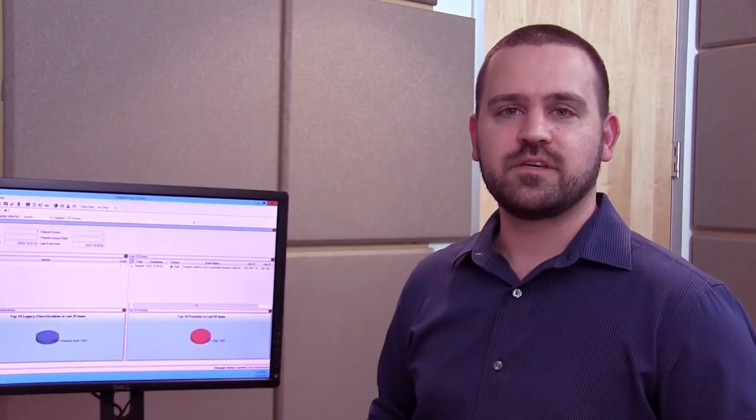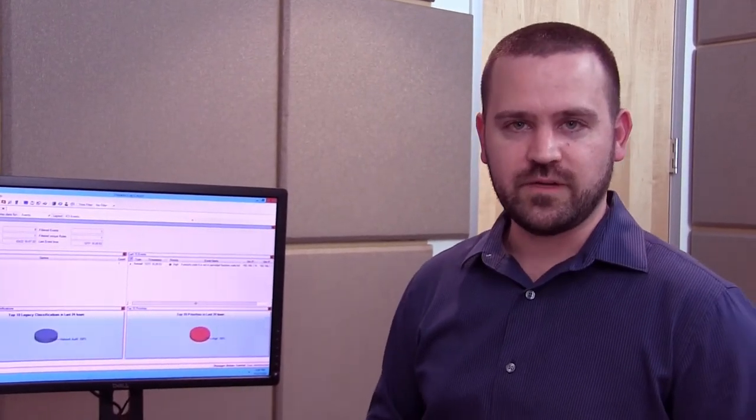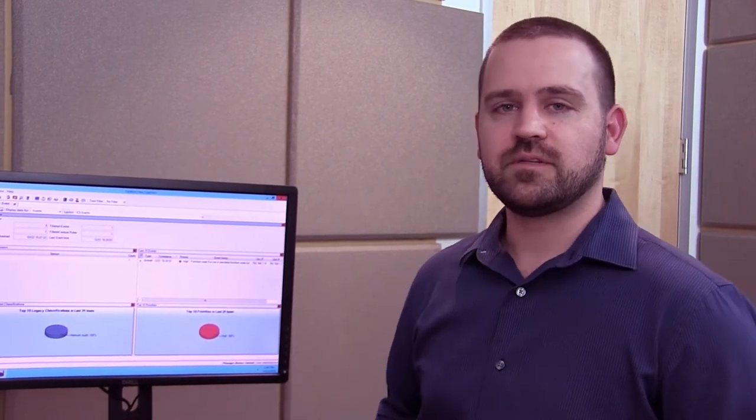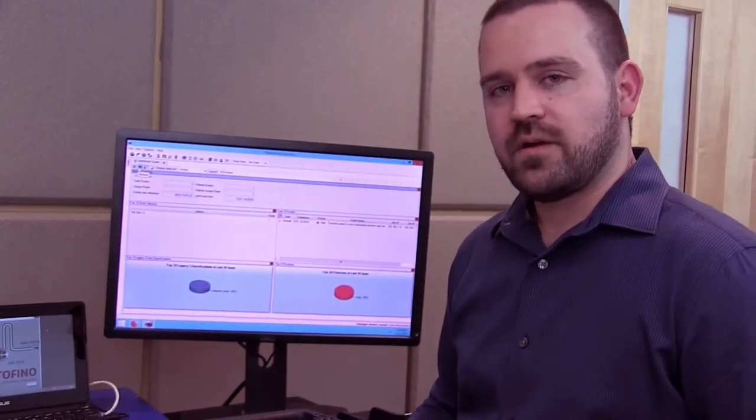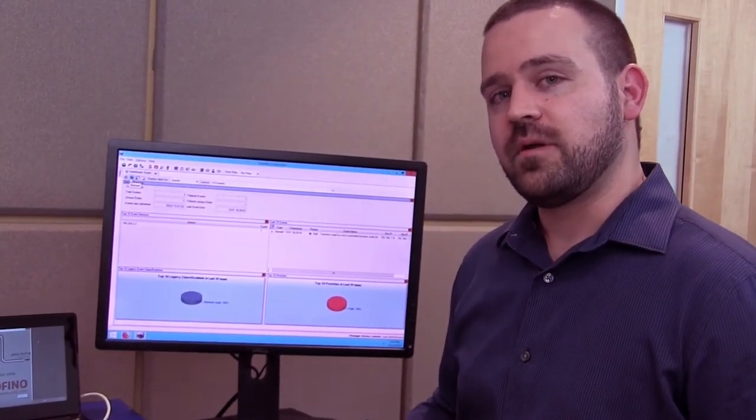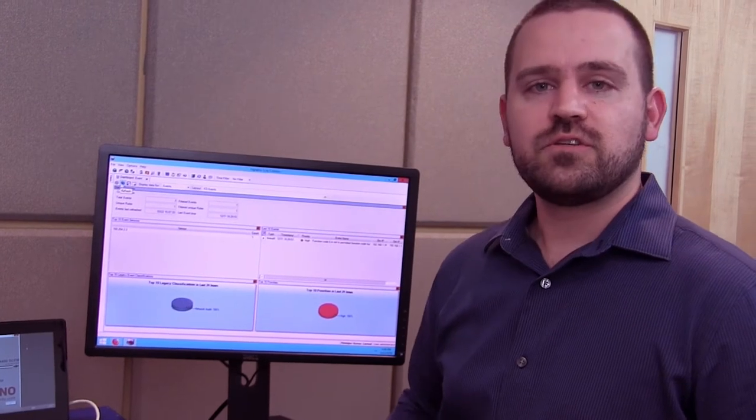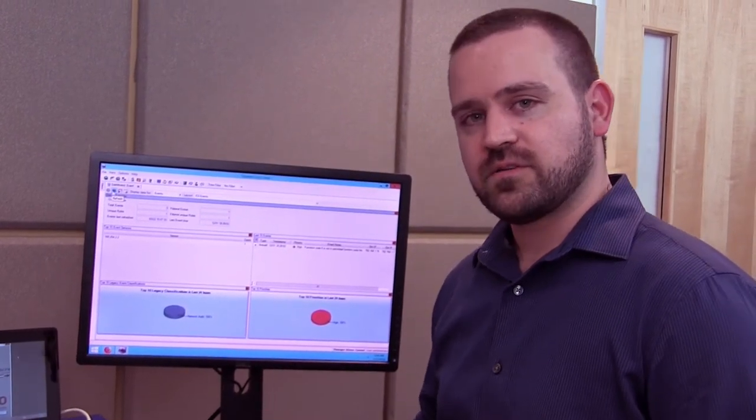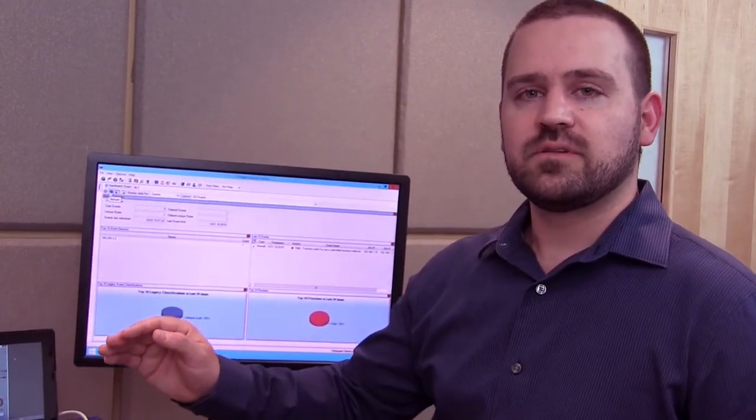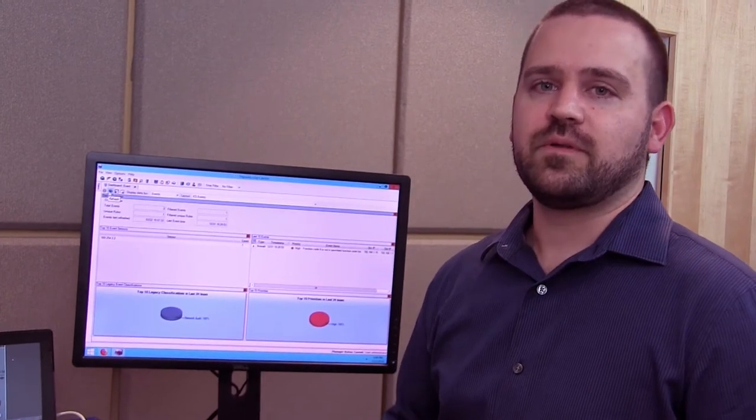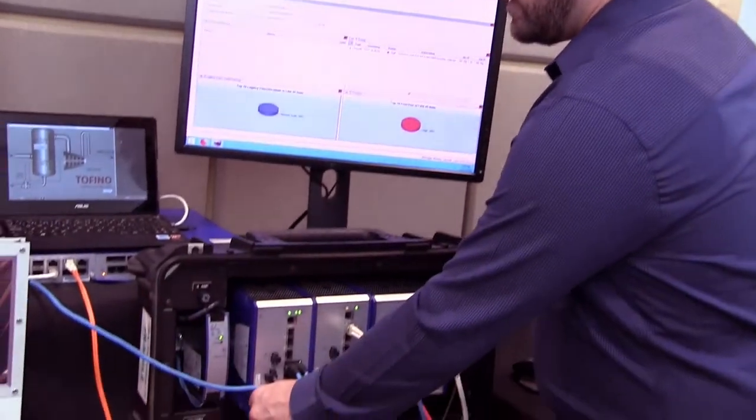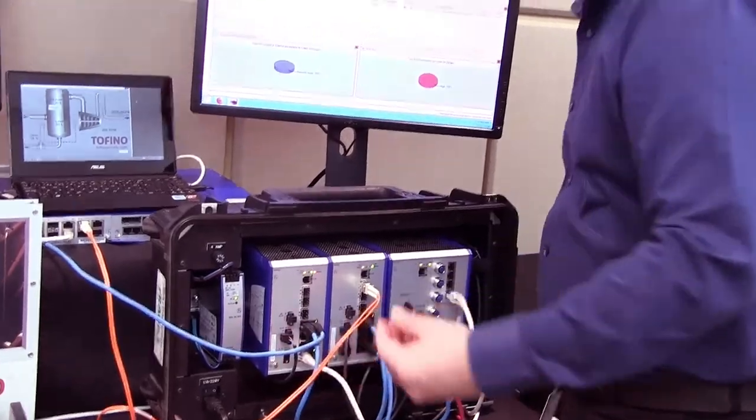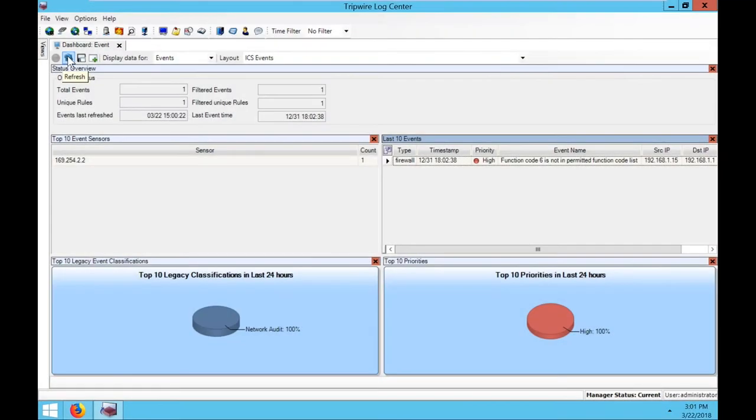It's important to note the security can also be very operational in nature. For example, in most industrial networks, we have redundancy built in everywhere, but one of the complaints I often get is if a redundant power supply goes down or if a primary power supply goes down, you actually don't know until two years later when the redundant power supply goes offline also. For example, if we pull this power supply to simulate an outage, we can come into Tripwire LogCenter and see very quickly that that power supply has failed and then know we need to go investigate this switch.